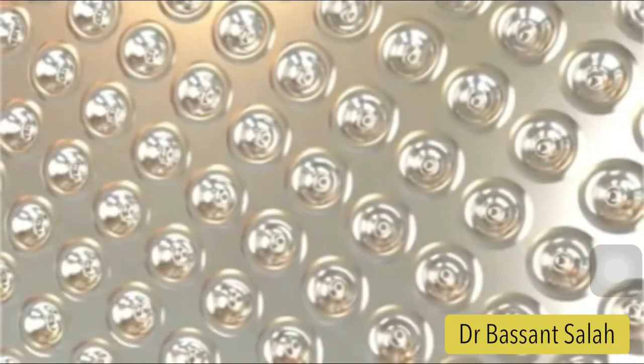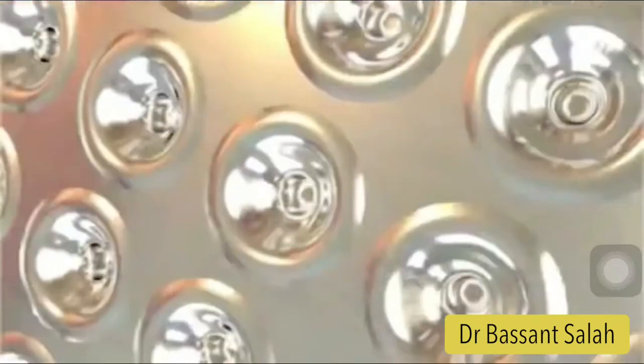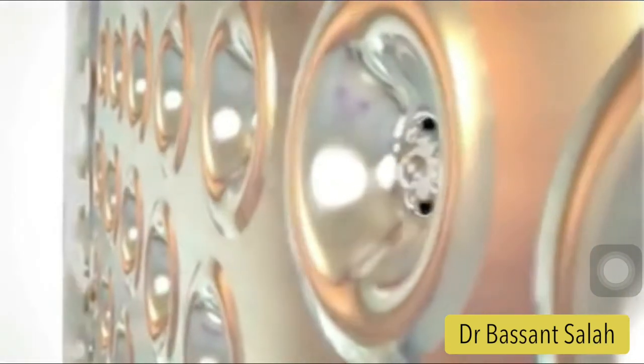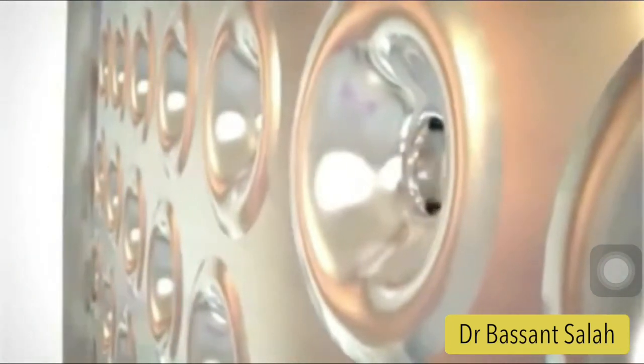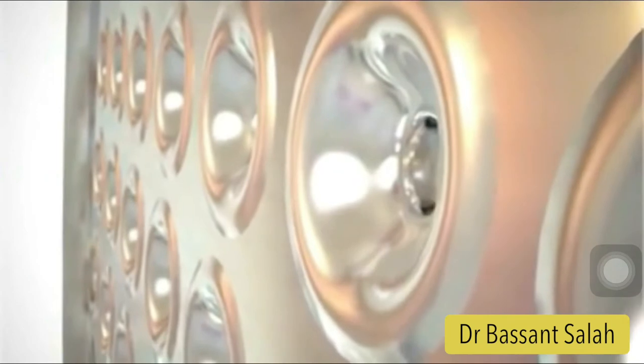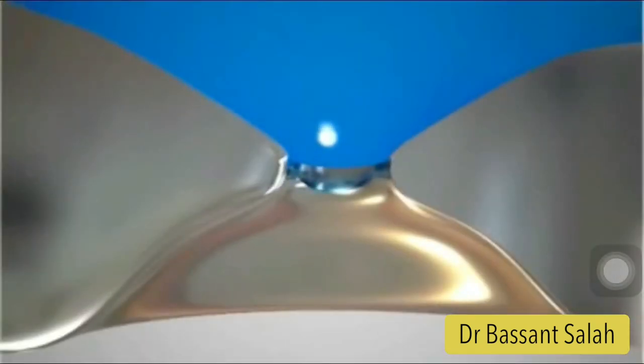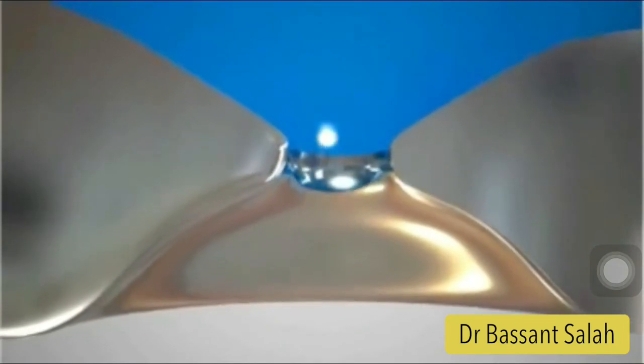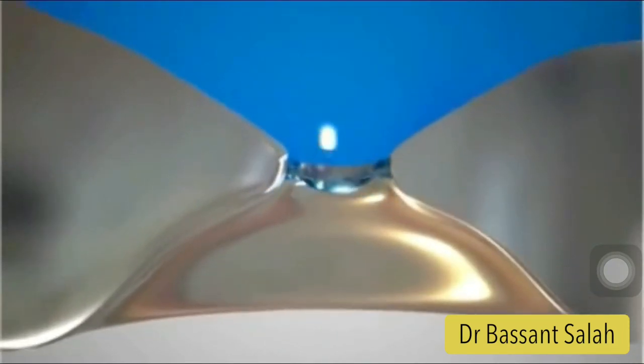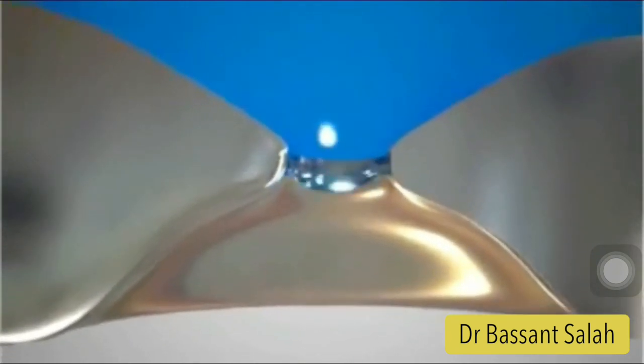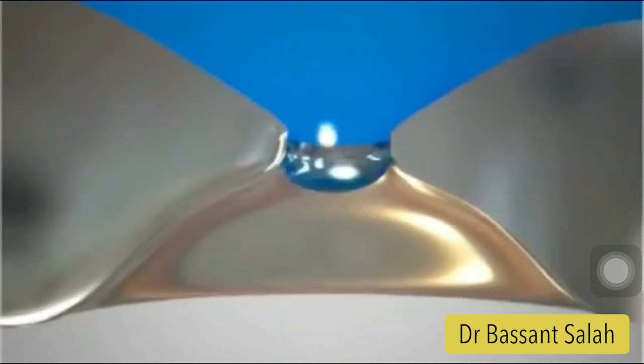As for the vibrating mesh nebulizer, it has a vibrating disc that is 1 centimeter in diameter, containing 1000 precision holes. Those precision holes are connected to a plate that moves up and down 1 micron in distance and vibrates about 120,000 times per second, creating an electronic micro pump. Those electronic micro pumps shear the medication into multiple particles of uniform size and shape.